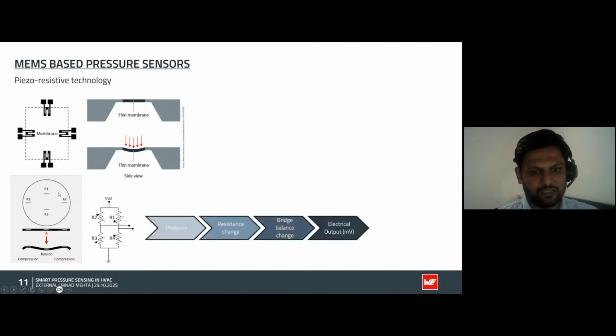So what we do is arrange the four piezoresistors in a normal Wheatstone bridge configuration. Whenever there is stress from the top side, the resistance changes. In normal operation, when we supply some voltage, the bridge is in a stable condition, but whenever there is stress, the resistance changes and the bridge becomes imbalanced, producing an output voltage drop. This voltage drop is directly proportional to the stress or pressure exerted on the top side—so pressure is converted into an electrical output in millivolts, and that's how the MEMS-based piezoresistive pressure sensor works.